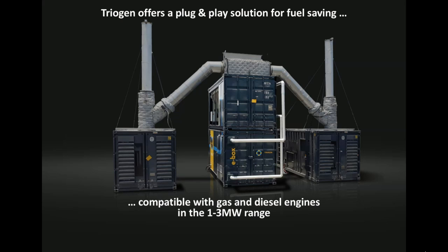What we can do is take the exhaust gas into our machine. The two containers in the middle, that's our equipment. We take the exhaust gas and put it through the top container, which is nothing but a conventional heat exchanger. It evaporates our working medium, and rather than escaping at 500 degrees, it goes to the ambient air at around 200 degrees. We then run the vapor we produce through a turbine, which at the heart of it is the same as any conventional power generation, any steam turbine. There's a few tricks why we can make it so compact and small and put it into containers—it's called ORC technology, an organic working medium. But that's just the magic within the system. At the heart of it, it's a turbine that drives a generator that produces power.